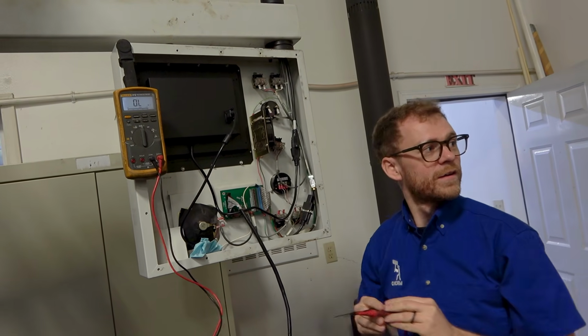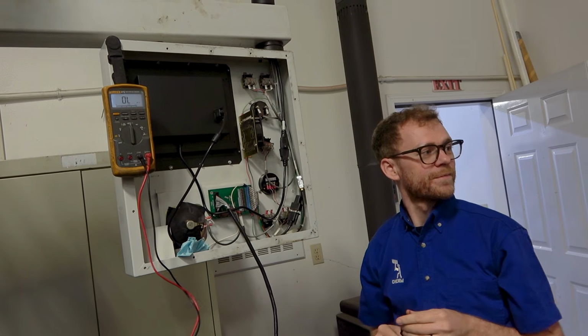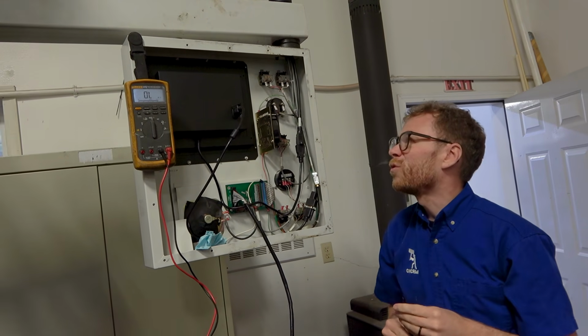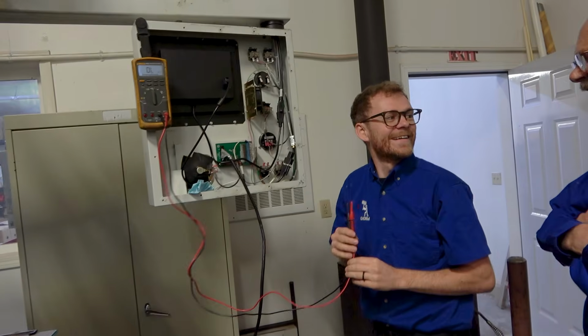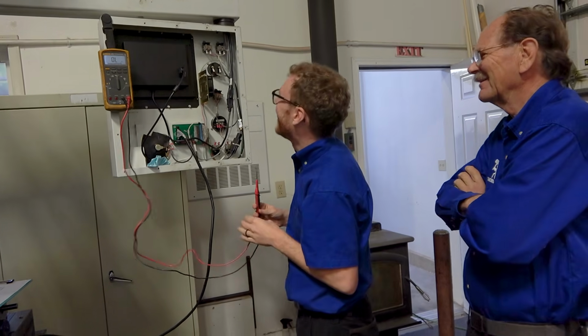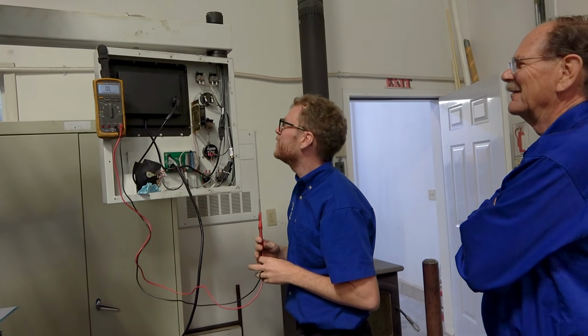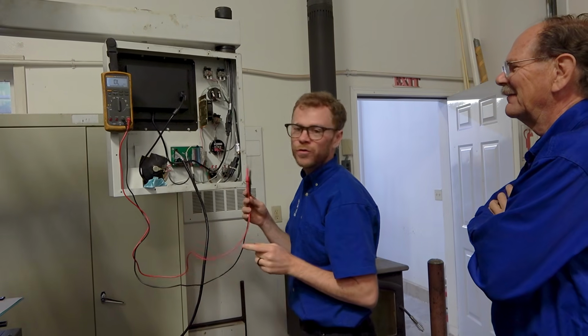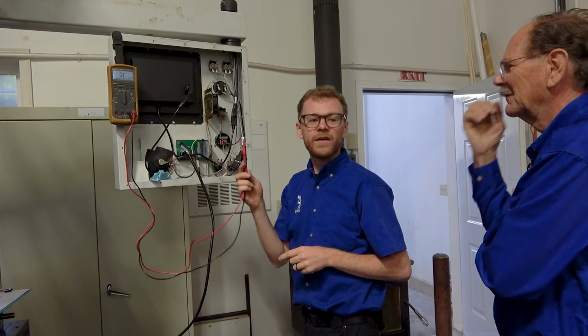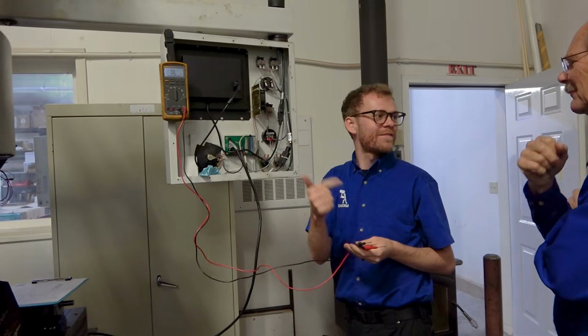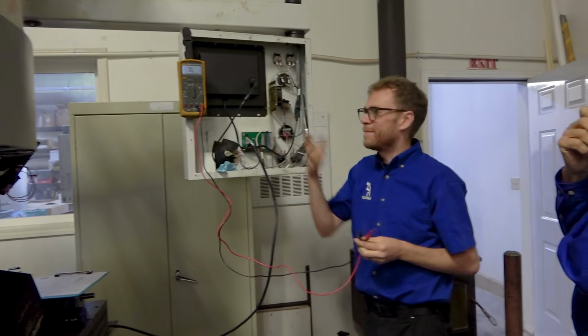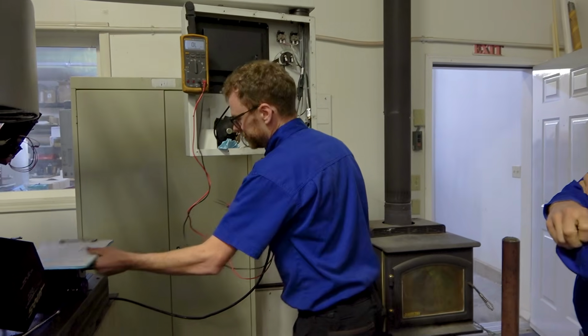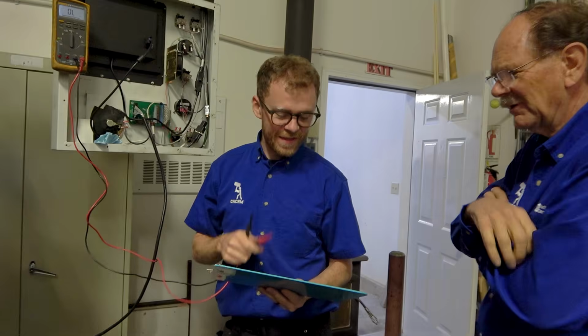You can measure resistance while the power is on it? Yeah. We're at 28 volts - I don't think I'd do it with 480. But yeah, I can do it here. If you get into DC voltage that's too high, it'll backfeed and you'll get negative resistance readings. I'm just looking for opens or closed. I don't think you could do that on an old analog meter, like the Simpson 260 - that doesn't work for this.